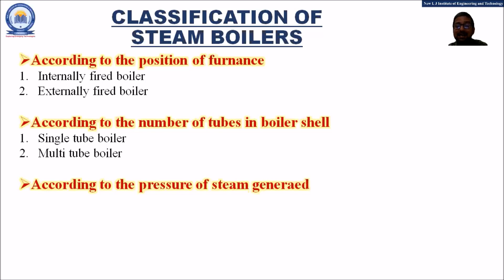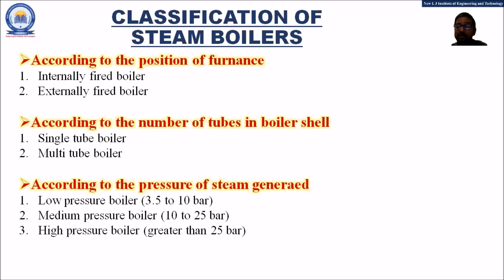The final and important classification of the steam boiler is according to the pressure of steam generated. That is the low pressure boiler, in which the pressure range is 3.5 to 10 bar. Second is the medium pressure boiler, where the pressure range is 10 to 25 bar. And third is the high pressure boiler, where the pressure of the steam generated is greater than 25 bar. So on the basis of the pressure of the steam generated inside the boiler, the boilers are classified as low pressure, medium pressure and high pressure boilers. So these are some of the basic classifications of the steam boilers.